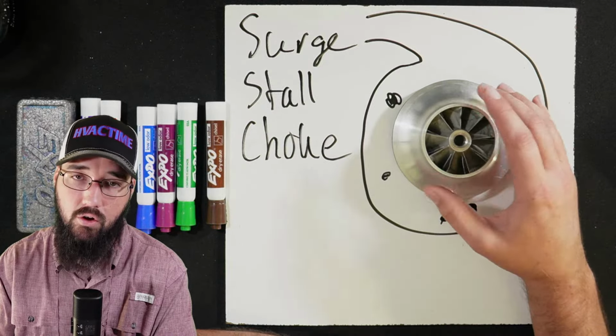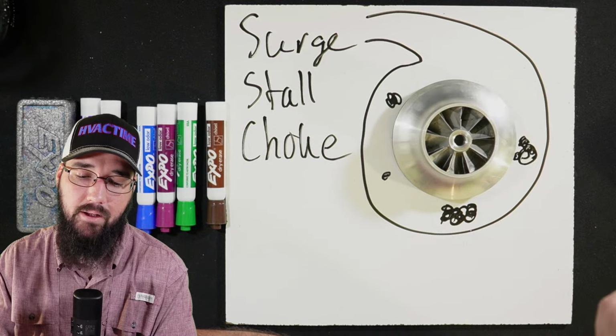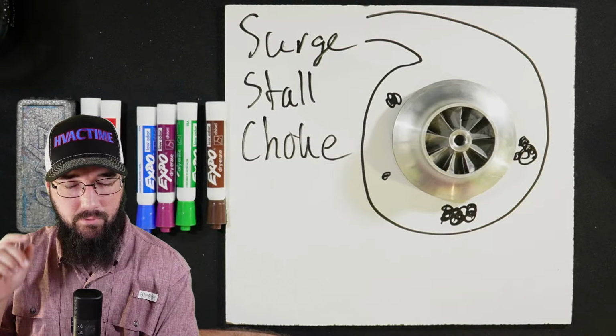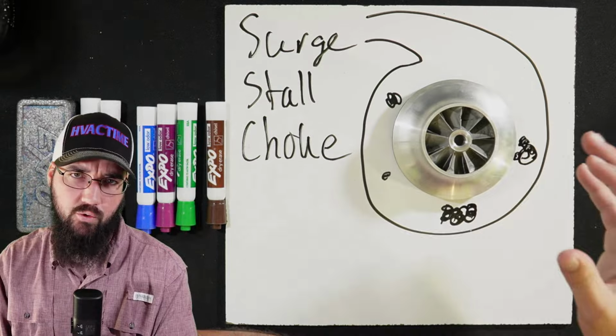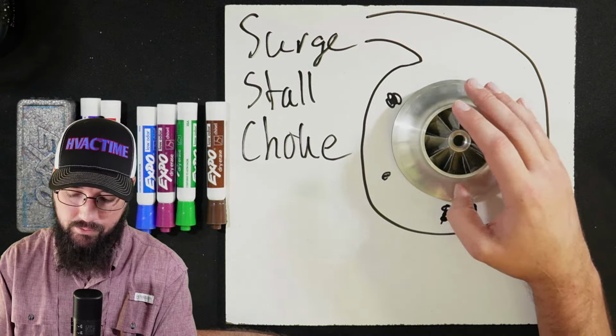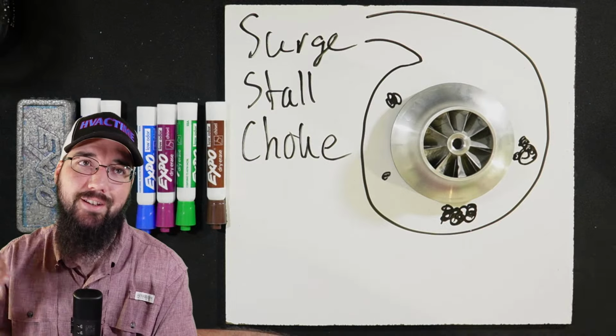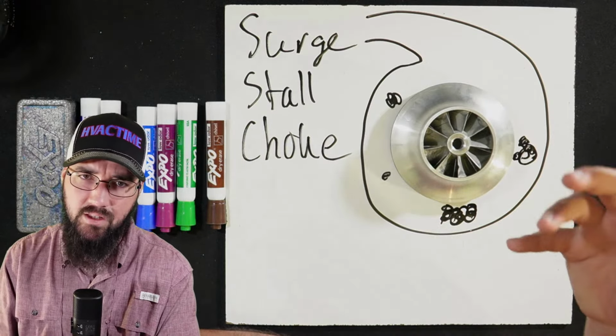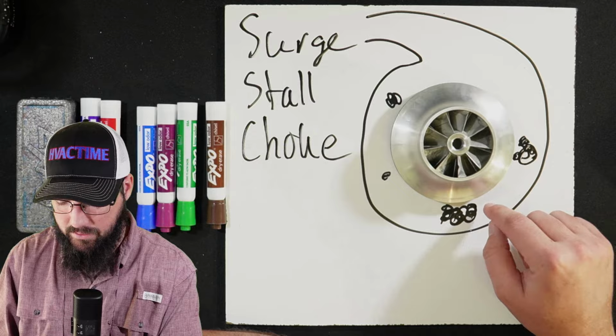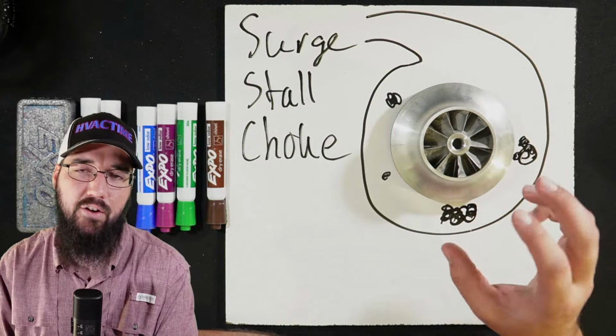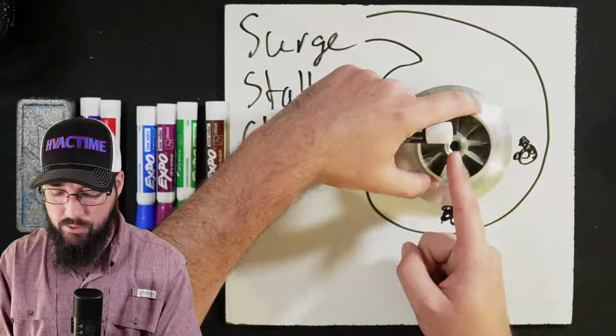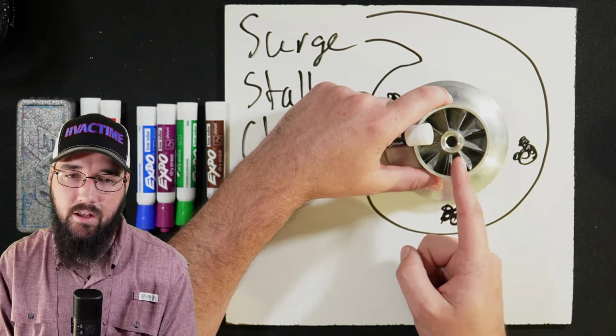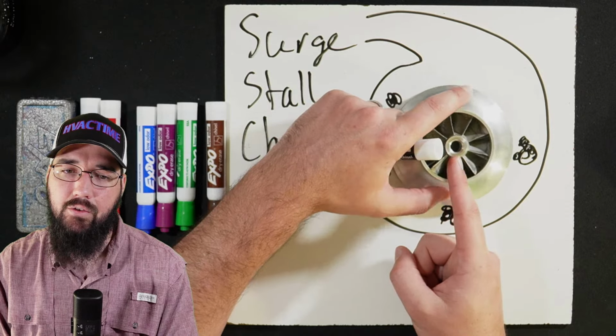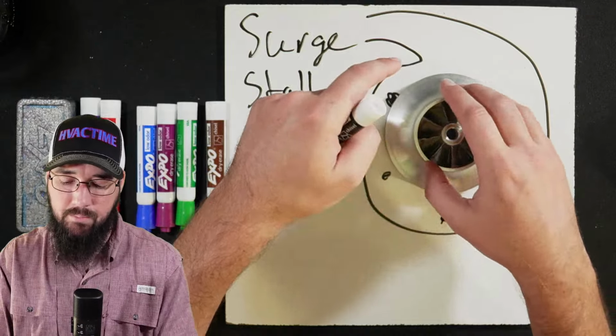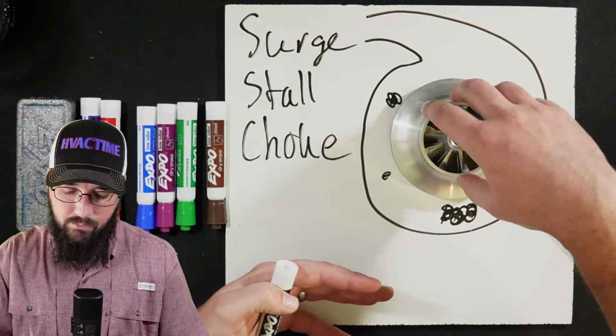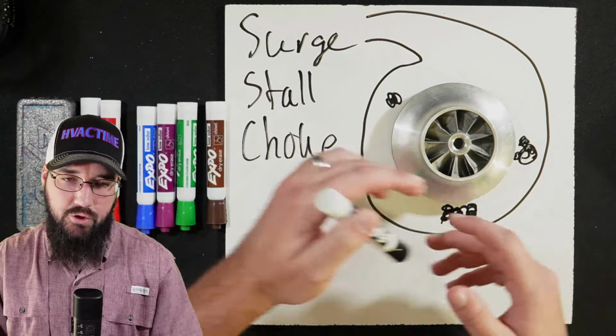That's why in a stall we can hear it, because it sounds like it's not quite a bearing noise, if you will, but there's just this low-end grumble coming from the compressor, and you can feel more vibration when it's happening, and that is the machine sitting in a stall state. That's where all that grumble is coming from. And that's because each of these points throws the impeller out of balance. And so right here, as it's rotating, whatever vane is lined up with this spot of the diffuser is where the imbalance is coming from. And then as it leaves that and begins to flow again, it rebalances. But that's our stall.